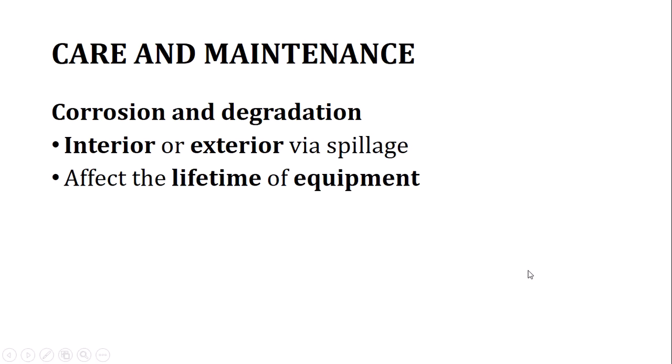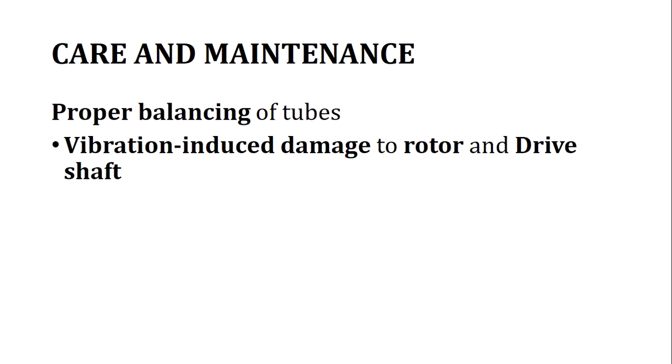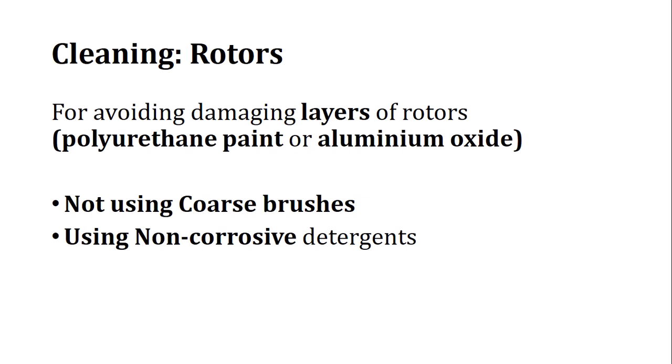Regarding care and maintenance of the centrifuge: corrosion on the interior or exterior from spillage can affect the equipment's lifetime and should be avoided. Proper balancing of tubes is required to prevent vibration-induced damage to the rotor and drive shafts. Any acidic or basic liquid should be cleaned promptly. Rotors typically have a protective polyurethane paint or aluminium oxide coating, and for washing, hard brushes should not be used — only non-corrosive detergent.